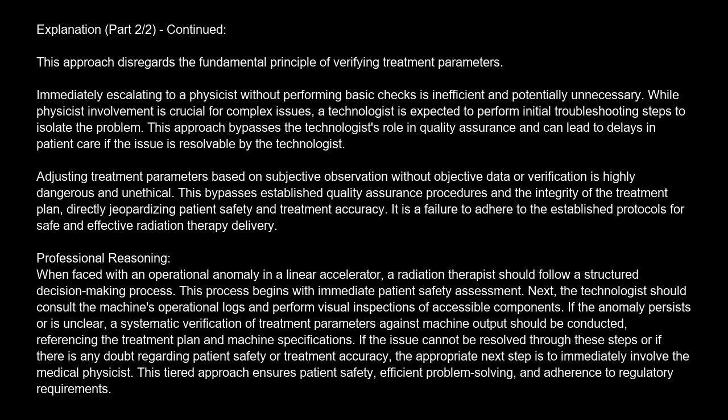Professional reasoning. When faced with an operational anomaly in a linear accelerator, a radiation therapist should follow a structured decision-making process. This process begins with immediate patient safety assessment. Next, the technologist should consult the machine's operational logs and perform visual inspections of accessible components. If the anomaly persists or is unclear, a systematic verification of treatment parameters against machine output should be conducted, referencing the treatment plan and machine specifications.